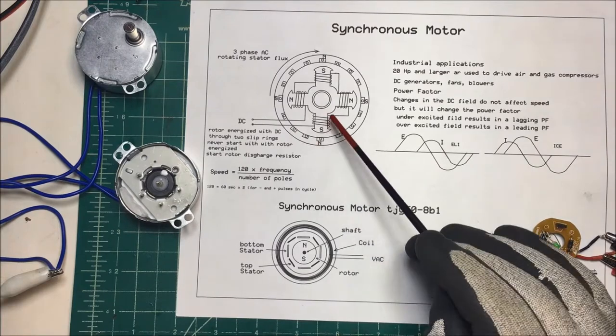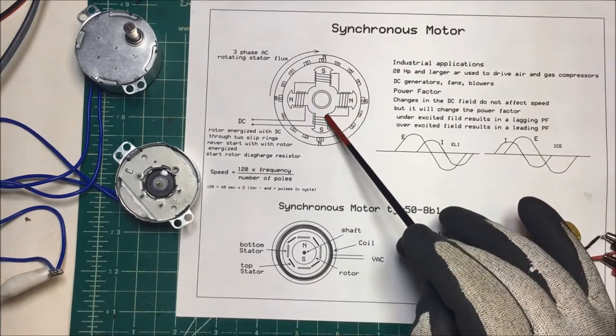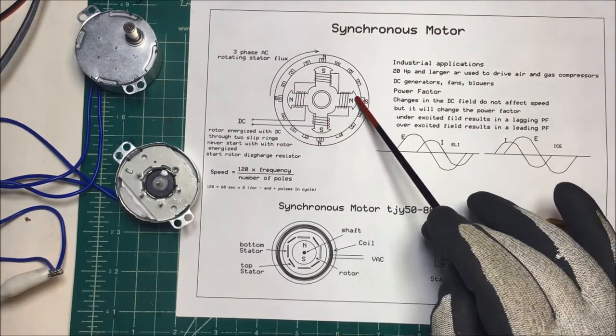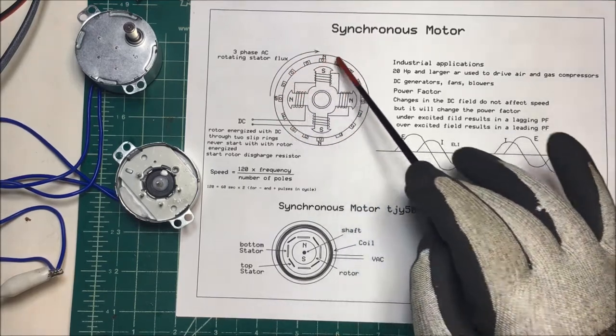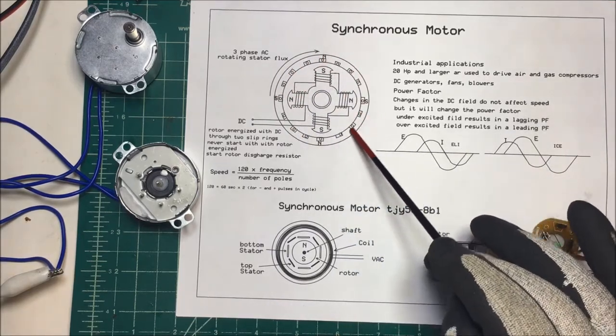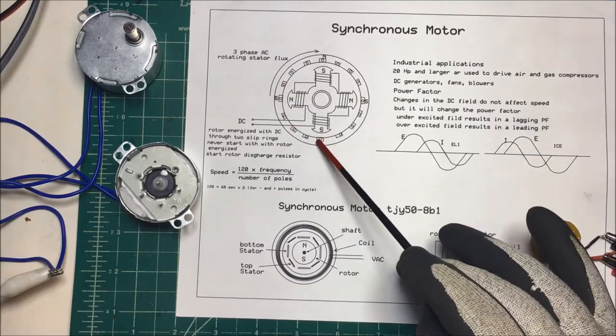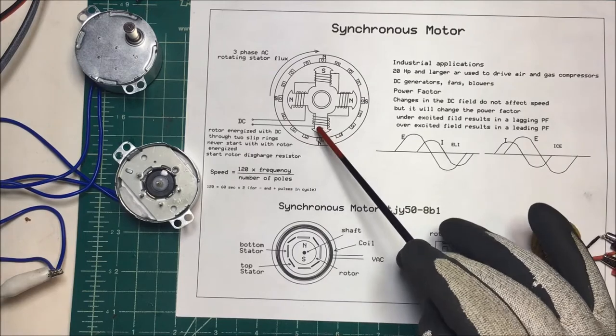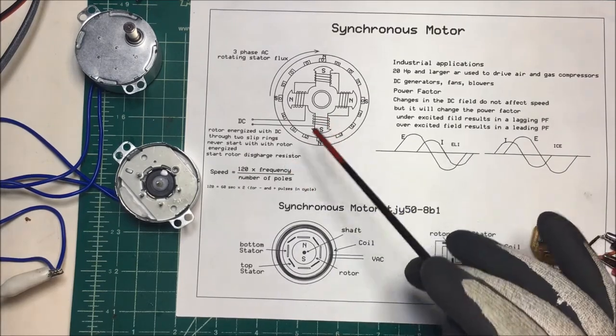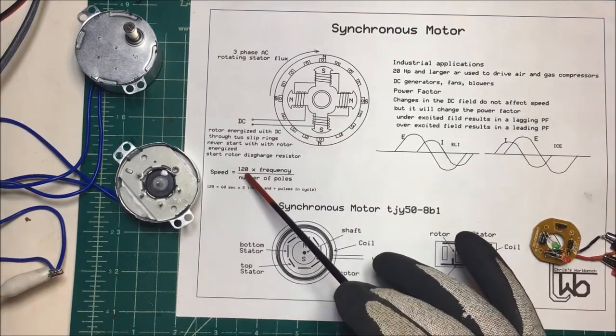So you set up this magnetic field in this rotor here, and that locks into this rotating flux around here, your three-phase rotating field, and it stays in sync with that. The speed is dependent on the frequency. For here it's 60 hertz, but to find the speed it's 120 times the frequency divided by the number of poles.